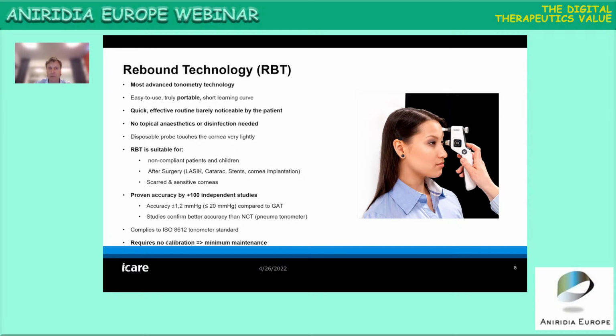Rebound technology, which I now refer to as RBT, is suitable for non-compliant patients and children especially. It can be used in cases where the eye has undergone surgery, and it is suitable for scarred and sensitive corneas. Its accuracy has been proven, the technology I'm talking about here, in more than 100 independent studies. It correlates very well with the Goldmann applanation tonometer. Studies also confirm it has actually good repeatability compared to a non-contact tonometer. And one thing, it requires no calibration.